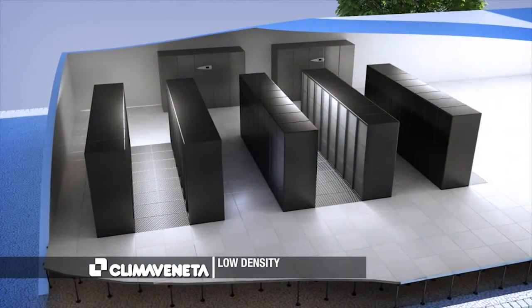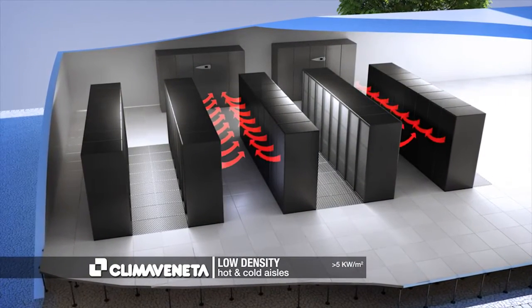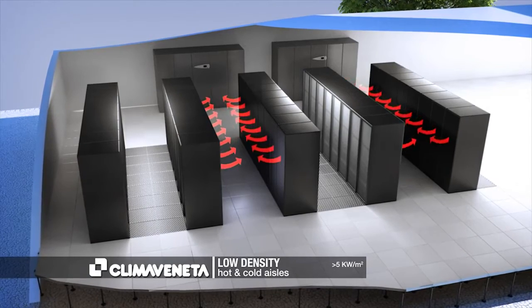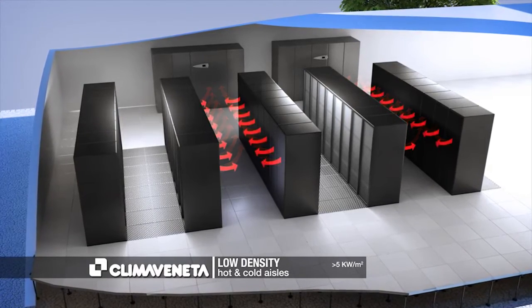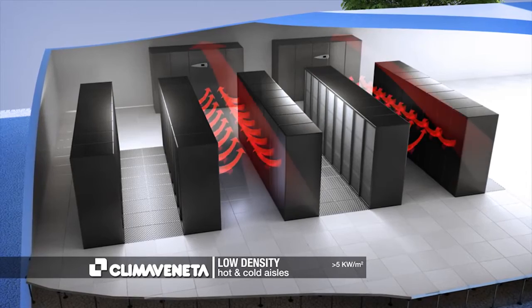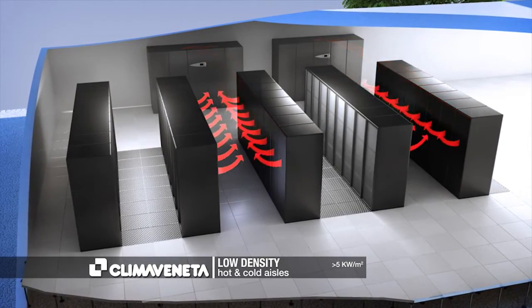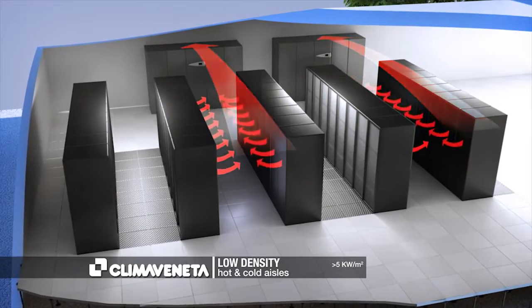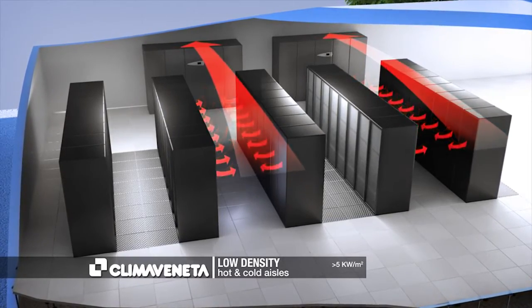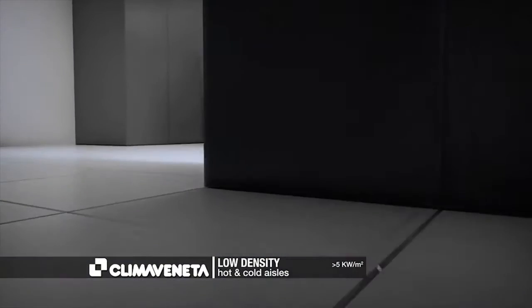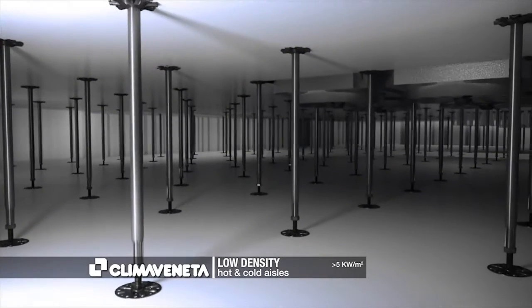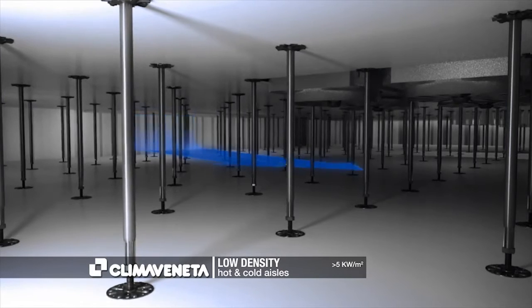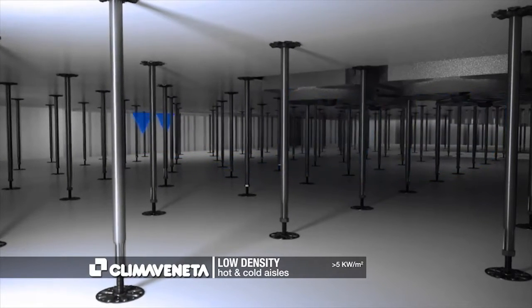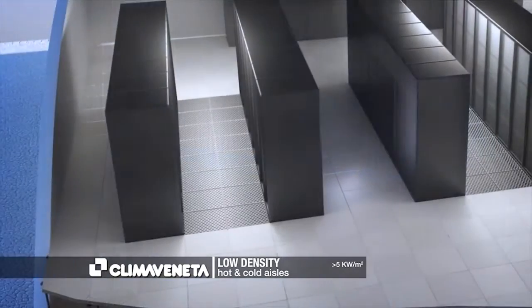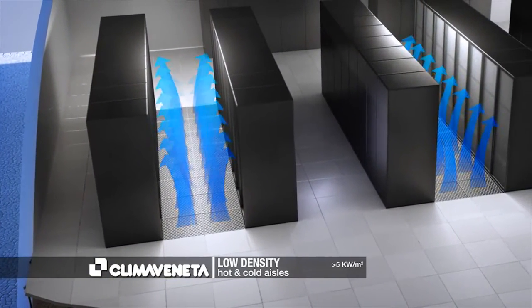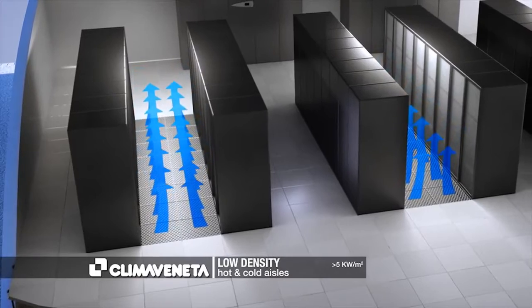Due to the unavoidable growth of computing demand, the design of a typical data center usually requires a low-density heat load and hot and cold aisles. This configuration provides a good balance between capital expenditure and cooling efficiency. The heat generated by servers goes straight to the Climaveneta CRAC units located on the perimeter. They cool the air and deliver it under the raised flooring, allowing the cold air to be distributed where it is needed in the room. Then cold air can easily reach the front of the rack.